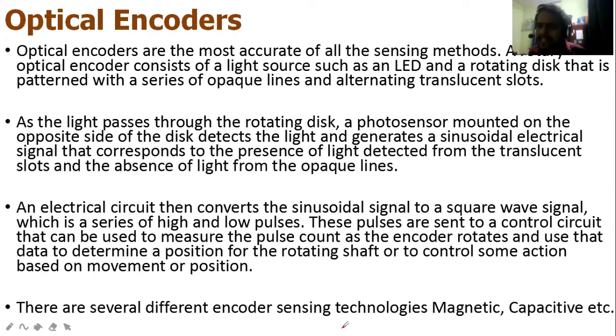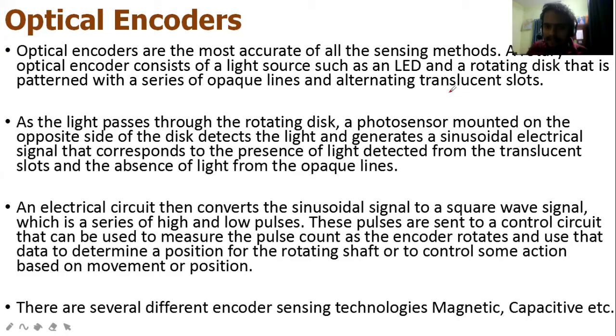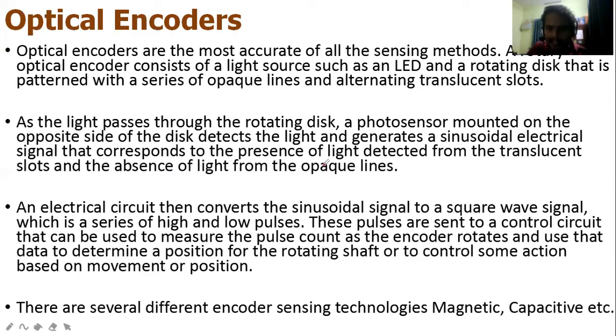Optical encoders are the most accurate of all sensing methods. A rotary optical encoder consists of a light source such as an LED and a rotary disc patterned with a series of opaque lines and alternating translucent slots. As light passes through the rotating disc, a photo sensor mounted on the opposite side detects the light and generates a sinusoidal electrical signal corresponding to the presence of light from the translucent slots and the absence of light from the opaque lines.